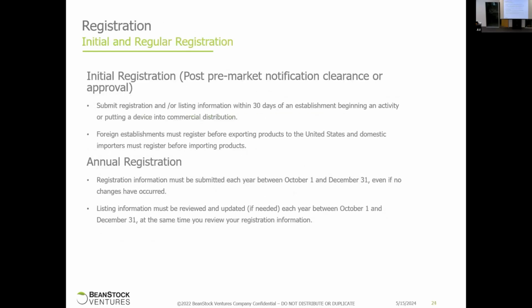Registration. So I mentioned before, before you actually can start selling your device, you do need to register with the FDA regardless of your device classification, regardless if you're exempt. There are different rules if you're class 2 or class 1, exempt or non-exempt, special controls, et cetera. So make sure you research what is applicable to your device. And this is required to be done annually. There's a fee associated with it. I don't want to say it's minimal because I know you guys are all startups, but don't quote me on it. It's about maybe $3,000 a year or something like that to register. So it's not as significant as the submission cost, but it's a cost nonetheless.